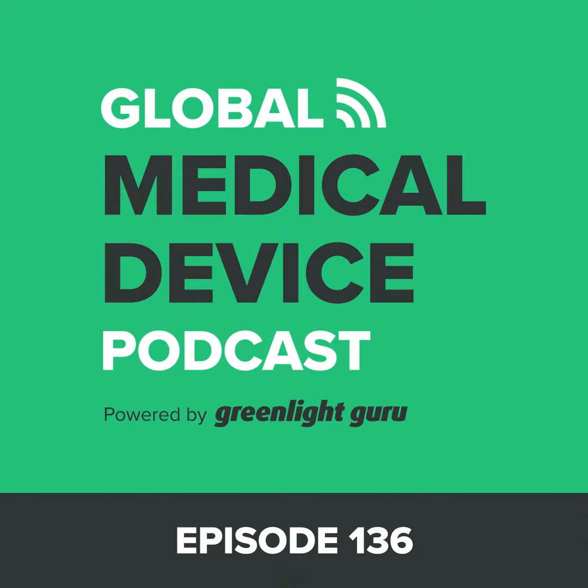If you don't qualify for eSTAR, because remember, you have to have software, it has to be in contact with body tissue and so on, so there are some limitations. If you don't qualify for eSTAR, you might consider the Quality in 510K Review pilot that I briefly alluded to at the beginning, which is an alternative. If you fit into one of those predetermined 40 or so product codes, you might go that route.